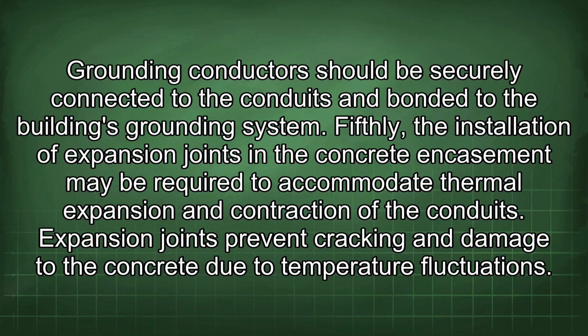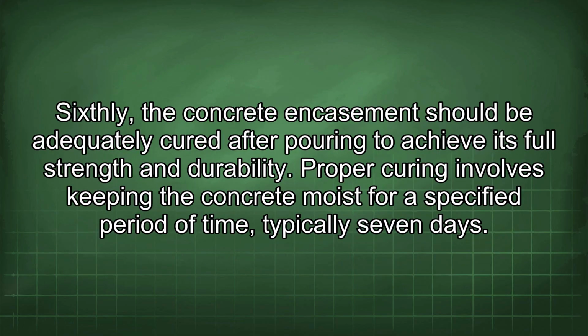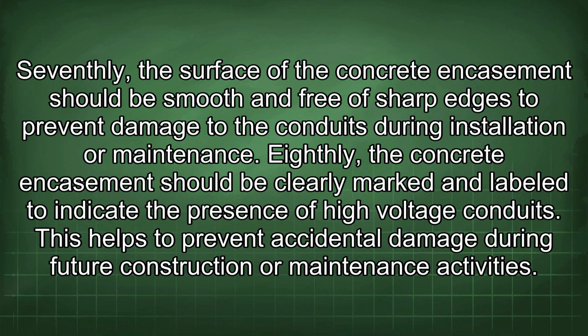Fifthly, the installation of expansion joints in the concrete encasement may be required to accommodate thermal expansion and contraction of the conduits. Expansion joints prevent cracking and damage to the concrete due to temperature fluctuations. Sixthly, the concrete encasement should be adequately cured after pouring to achieve its full strength and durability. Proper curing involves keeping the concrete moist for a specified period of time, typically 7 days. Seventhly, the surface of the concrete encasement should be smooth and free of sharp edges to prevent damage to the conduits during installation or maintenance.